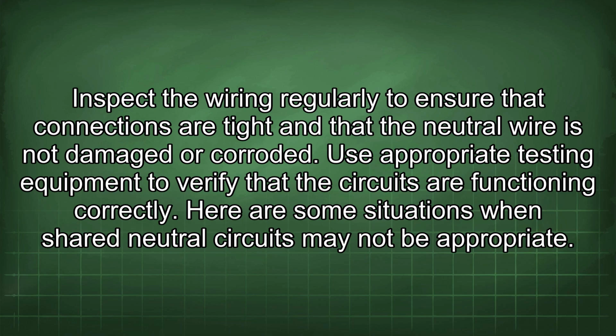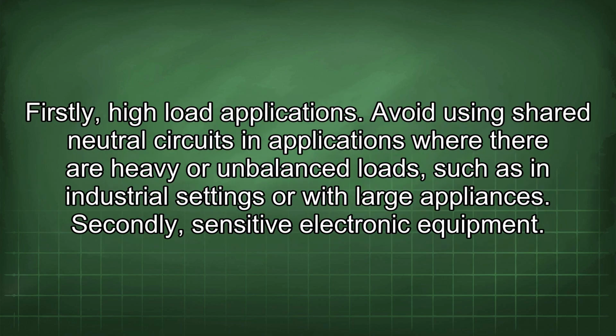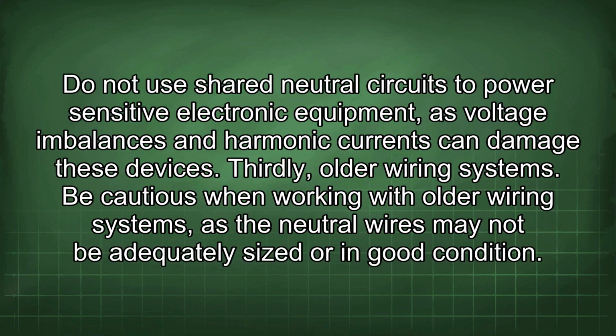Here are some situations when shared neutral circuits may not be appropriate. Firstly, high-load applications. Avoid using shared neutral circuits in applications where there are heavy or unbalanced loads, such as in industrial settings or with large appliances. Secondly, sensitive electronic equipment. Do not use shared neutral circuits to power sensitive electronic equipment, as voltage imbalances and harmonic currents can damage these devices. Thirdly, older wiring systems. Be cautious when working with older wiring systems, as the neutral wires may not be adequately sized or in good condition.